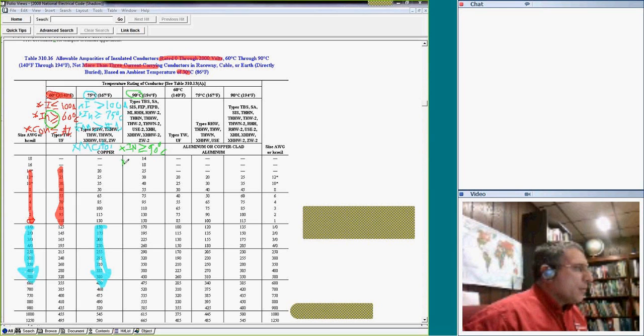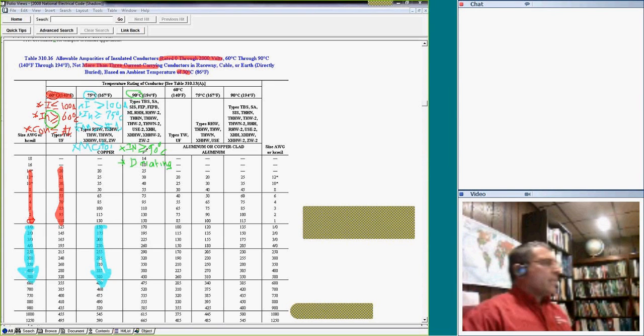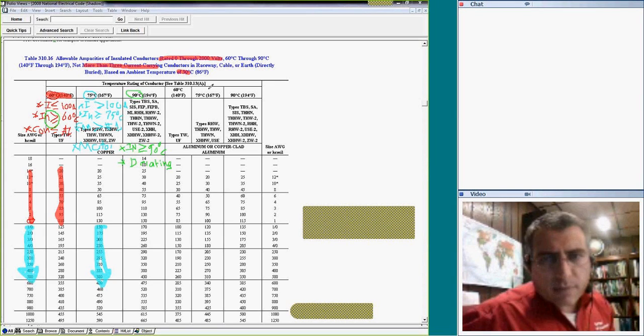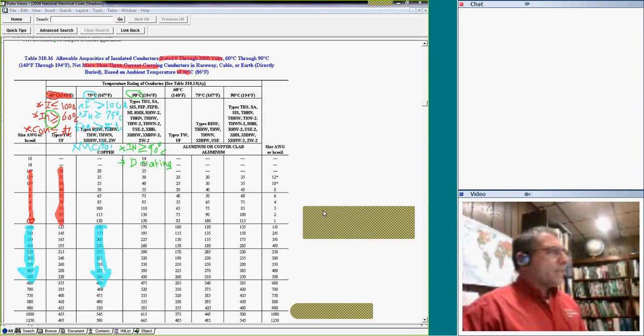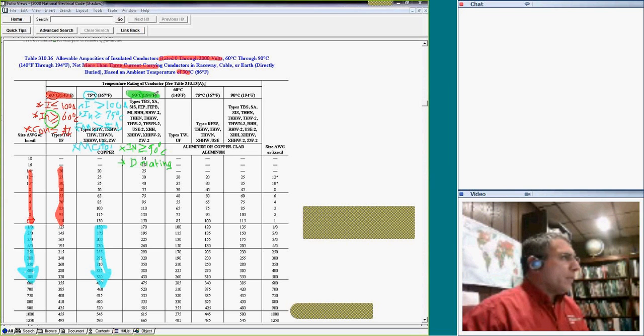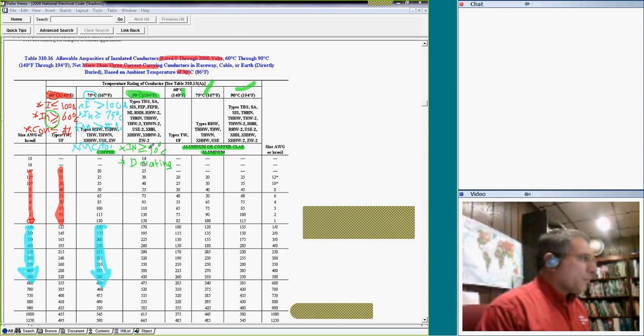Number two, you use it only for derating. You will never ever, my friend, size based on the 90-degree column. You always use it for derating. Always use it for derating. And I'm showing the copper here, but the aluminum is the same. This one, as you know, is aluminum, and this is for copper or aluminum.